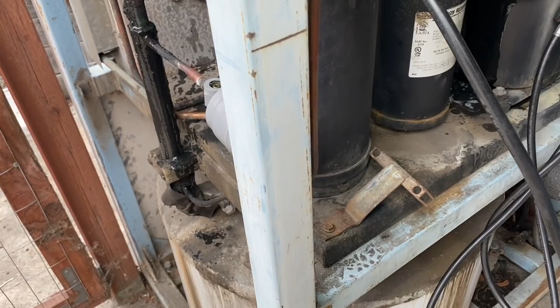I couldn't film a bunch because the customer was right there. So I was picking up a detection with the leak detector where it looked oily on that suction line, but it was weird because it didn't show any bubbles. But I could hear a leak, and I found it where the liquid line went into the heat exchanger. There's a liquid line heat exchanger right there. I got that brazed up, changed the dryer sight glass combo, and flowed a bunch more solder on that suction line joints. She held pressure and pulled a good vacuum. Now we're recharged and back up and running.